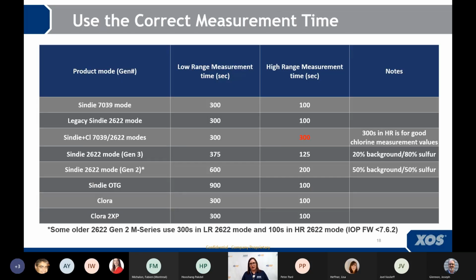Make sure you use the correct measurement time. If your sample is stable, a longer measurement time will get you more precise results. Typically in low range, this is a 300-second measurement time, and typically it's 100 seconds in high range. Of course, if you're running a 2622 analyzer, this will have some added time due to background measurement.